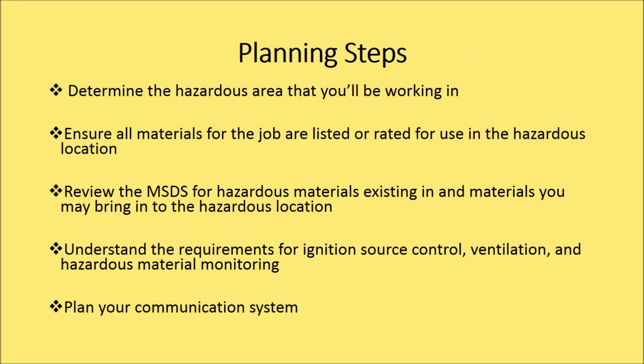Planning steps. Determine the hazardous area that you'll be working in, keeping in mind that a given installation or task may require work in unclassified areas. Be sure to discuss any questions you may have with your supervisor. Do not assume anything. Ensure all materials for the job are listed or rated for use in the hazardous location in which you will be using or installing them.